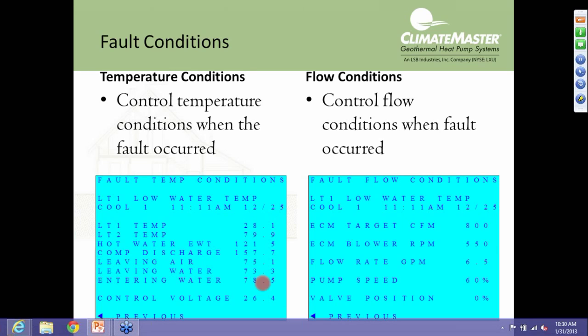So again, we can go on down. If this was a real world situation, we could see if anything else was out of whack, entering, leaving water, that kind of thing. Control voltage. We can look at our flow conditions. Again, airflow, water flow, pump speed. If you've got a valve, it'll show valve position.